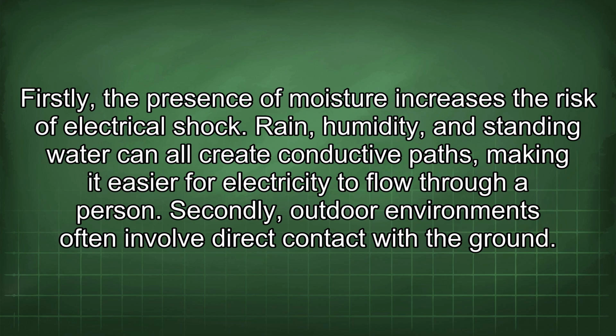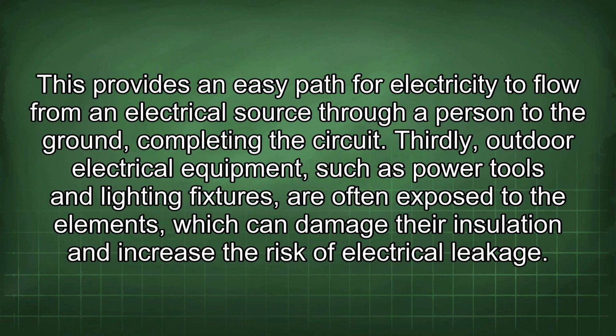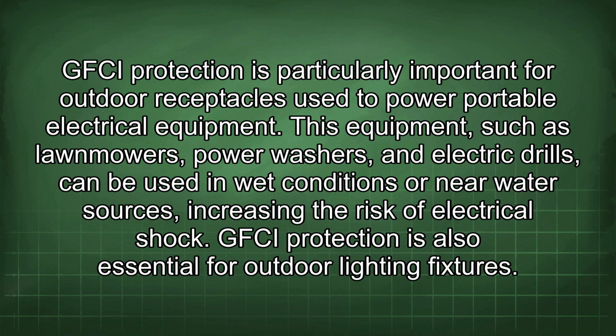Secondly, outdoor environments often involve direct contact with the ground. This provides an easy path for electricity to flow from an electrical source through a person to the ground, completing the circuit. Thirdly, outdoor electrical equipment, such as power tools and lighting fixtures, are often exposed to the elements, which can damage their insulation and increase the risk of electrical leakage. GFCI protection is particularly important for outdoor receptacles used to power portable electrical equipment. This equipment, such as lawnmowers, power washers, and electric drills, can be used in wet conditions or near water sources, increasing the risk of electrical shock.